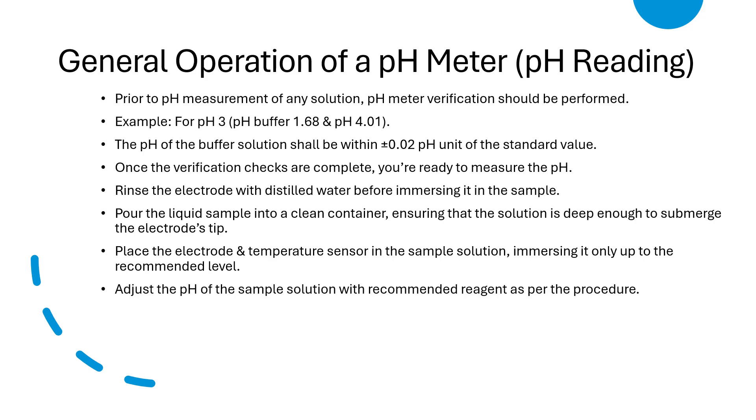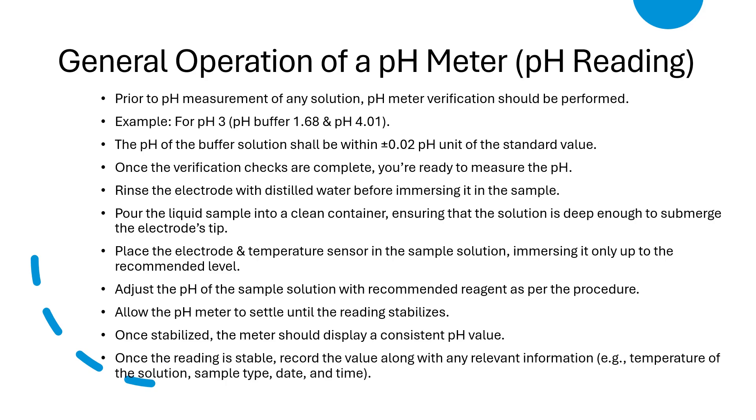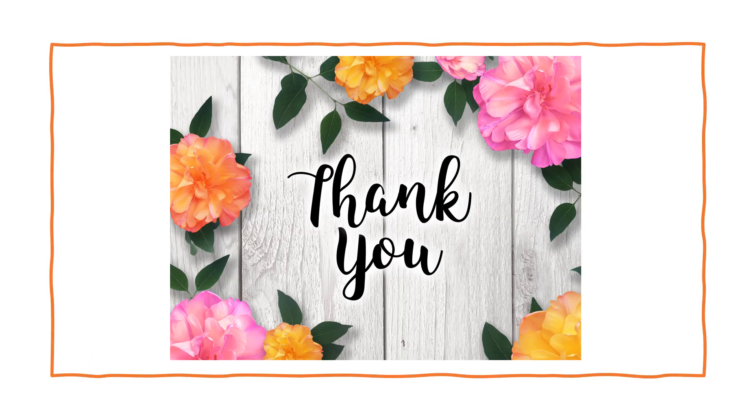Adjust the pH of the sample solution with the recommended reagent as per the procedure. Now allow the pH meter to settle until the reading is stabilized. Once stabilized, the pH meter should display a consistent pH value. Once the reading is stable, record the value along with any relevant information: temperature of the solution, sample type, date, and time. Friends, this is all about the general overview of the pH meter instrument.